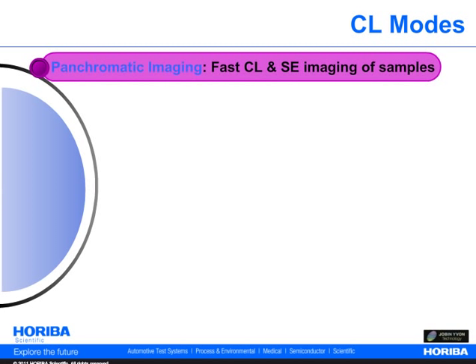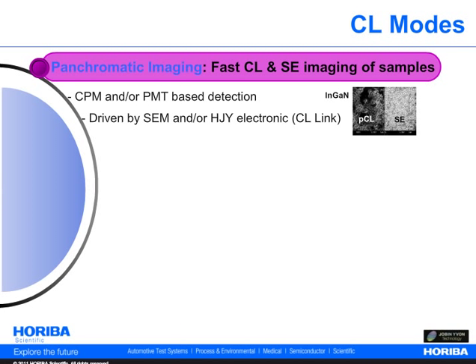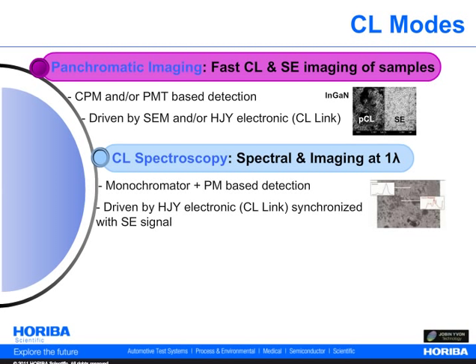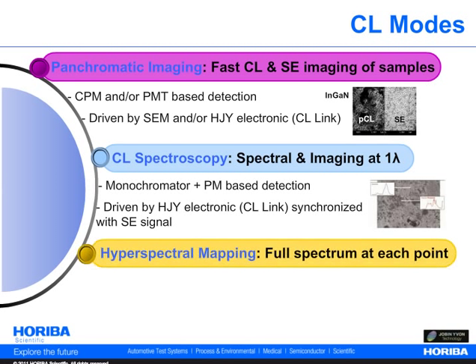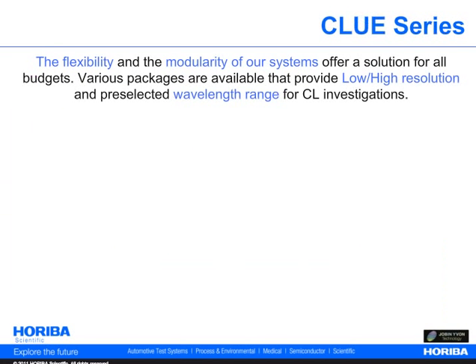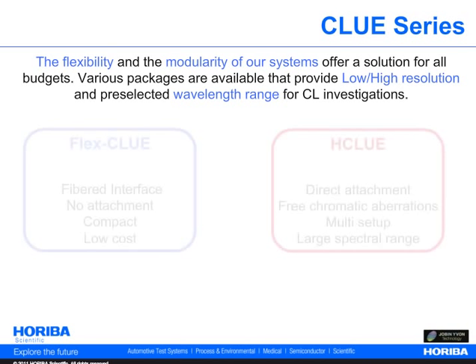The first is the panchromatic CL imaging mode, enabling fast and simple localization of the CL light emitted by the sample. This provides fast and effective visual information prior to a full investigation. The CL spectroscopy mode uses a monochromator to provide spectroscopic and imaging information of the CL light emitted by the sample. Finally, the hyperspectral CL mapping mode provides a simultaneous multi-wavelength spectrum at each point of the sample using CCD detection. The CLUE series includes the Flex-CLUE and the H-CLUE.